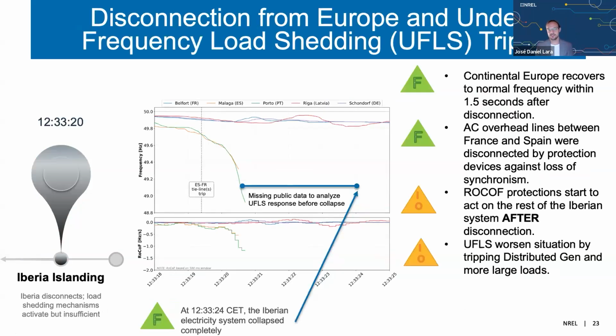And then finally, in the last stage, close to the blackout, here is where we now actually see that the line between France and Spain trips. Now that's kind of like the death knell of the Iberian system, where now we can see this rapid decrease in frequency. The overhead lines between Spain and France get disconnected, and now we actually see the rates of change of frequency that could explain this disconnection of more units. And one of the other pieces that happens here is that due to the under frequency load shedding protections in the Spanish system, because it's protecting against this loss of frequency, it probably worsens the speed of change at which the frequency drops, because you're losing all of this huge generation that was operating at the time.